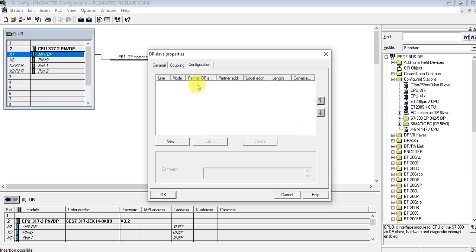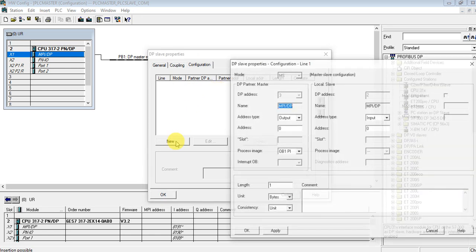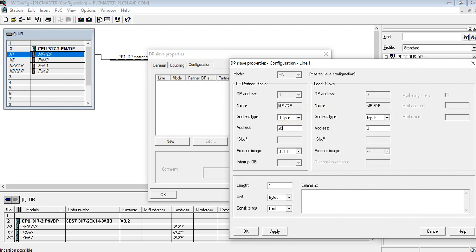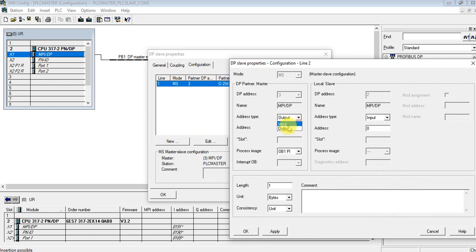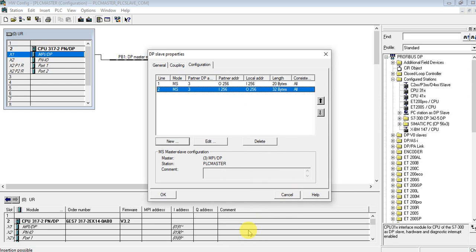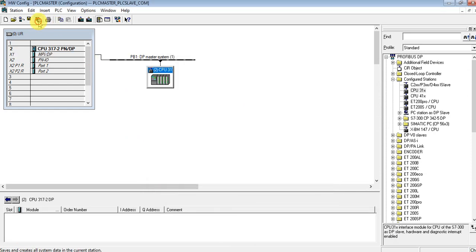We can also configure the input and output addresses here. The address we will use is 256. This one is the input and this is the output, and the length will be 20 bytes — I'm going to send 20 bytes from PLC one. For receiving, let's create another row: input address 256, output address 256, and we can receive 32 bytes. Great — now save and compile.